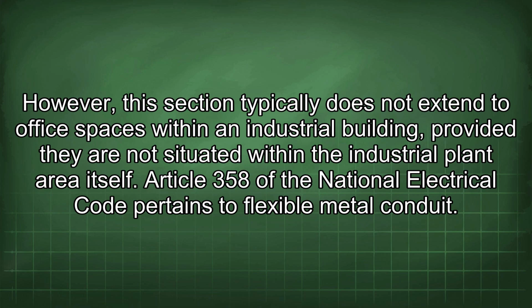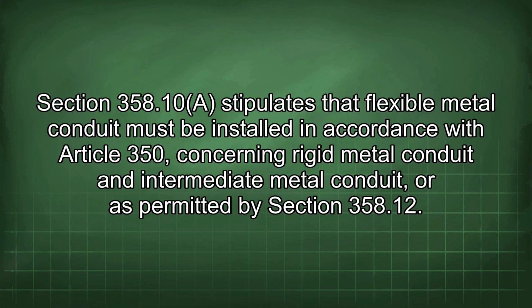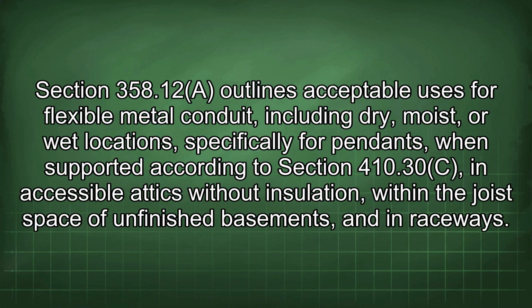Article 358 of the National Electrical Code pertains to flexible metal conduit. Section 358.10 stipulates that flexible metal conduit must be installed in accordance with Article 350 concerning rigid metal conduit and intermediate metal conduit, or as permitted by Section 358.12. Section 358.12 outlines acceptable uses for flexible metal conduit, including dry, moist, or wet locations, specifically for pendants, when supported according to Section 410.30(C), in accessible attics without insulation, within the joist space of unfinished basements, and in raceways.